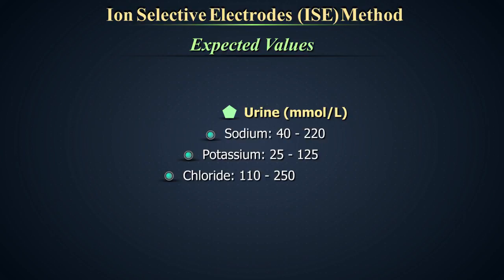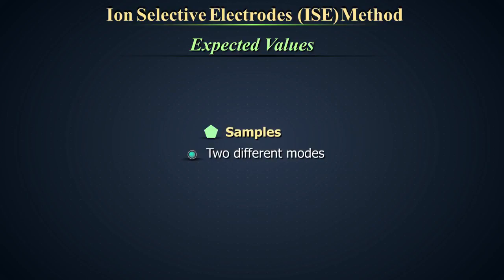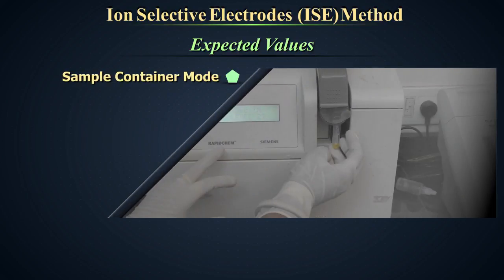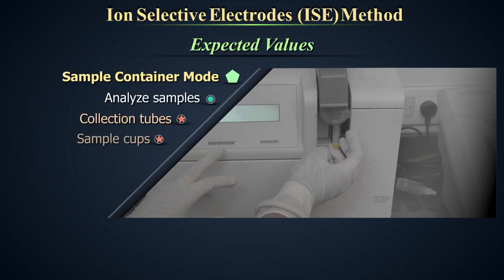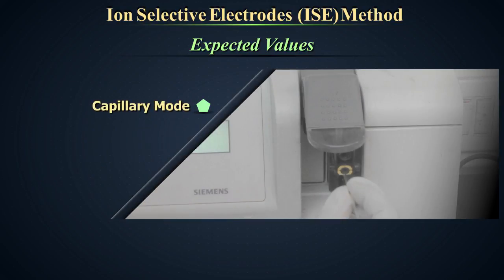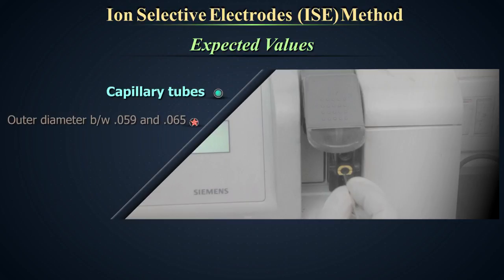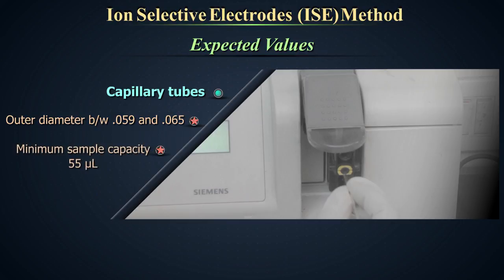In this instrument, samples can be run in two different modes. Sample container mode is to analyze samples from collection tubes, sample cups or syringes. Capillary mode to analyze samples from capillary tubes. Capillary tubes must have an outer diameter between 0.059 and 0.065 and a minimum sample capacity of 55 microliters.